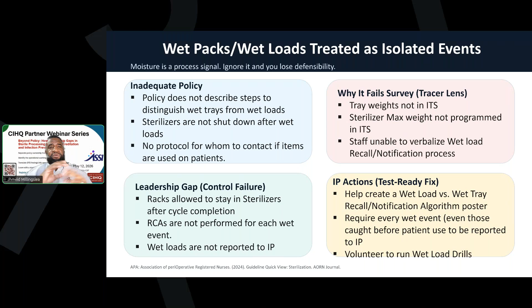IUSS, or shortened dry time for convenience, equals a QAPI failure signal. We used to call it flash. Shortened dry times, depending on your accreditation agency, what I know is exactly what the FDA says about it, what AAMI says about it, and what the Joint Commission says about it. So don't let the vendor tell you something you may not be able to defend on surveys.